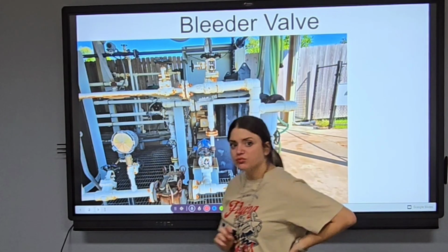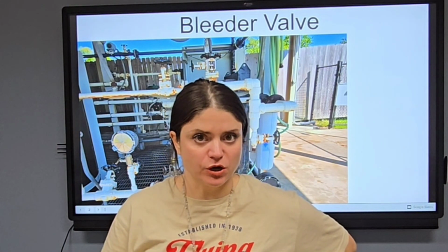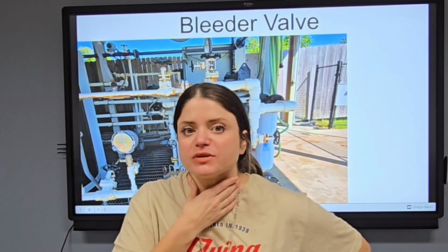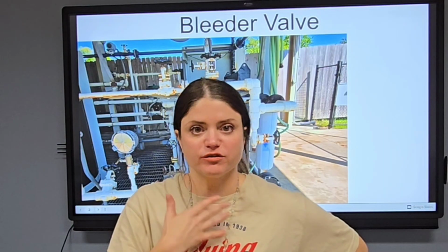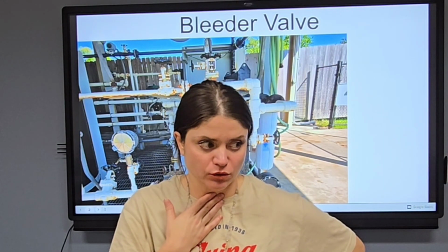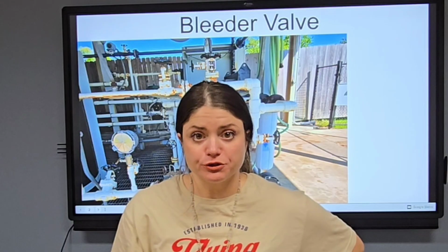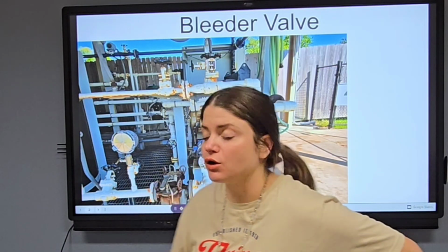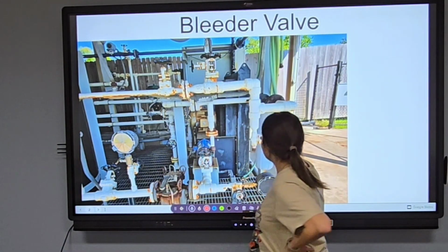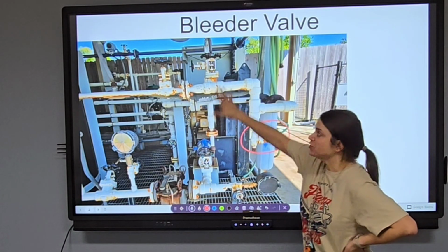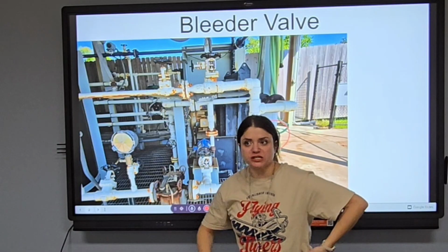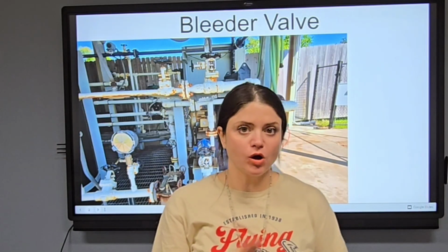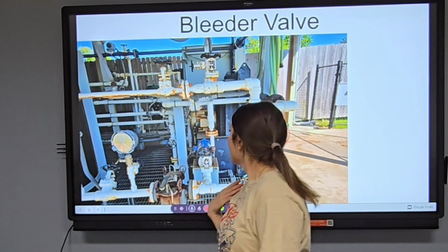Now, this is important. The purpose of a bleeder valve is not to bleed out your system, okay? In the same sense, the purpose of your throat is not to hold all of your blood in. But if something happens to your throat or your jugular, you're going to lose blood, right? You're going to bleed out. So, same concept. If I open this while my unit was running, I will bleed out my entire unit. That is not the purpose of it. If we were to open it during normal operations, we would end up bleeding out our whole unit.